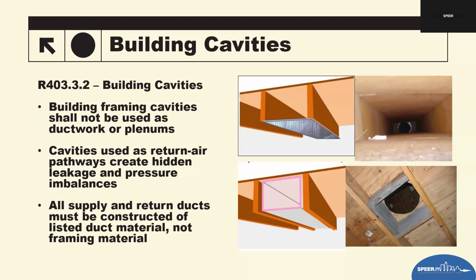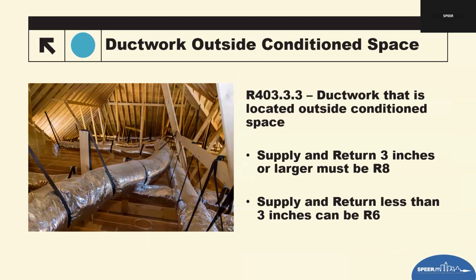Bottom line, framing cavities are not ducts. They're not air barriers. They're not pressure rated. They're not insulated. So the IECC enforces this to prevent hidden leakage, reduce moisture risks, and improve overall HVAC system performance. Again, this is what the book says. I've seen a lot of cities amend this and say you can use it as return but not supply. So whatever city you're in, make sure you find out how they've amended this and what they actually are going to require or not allow.